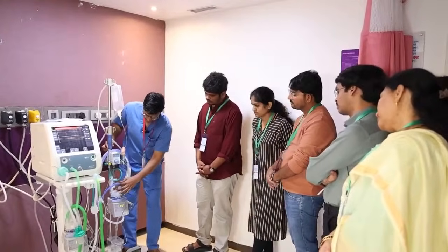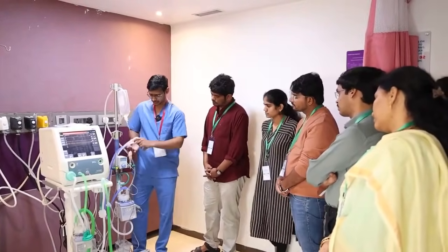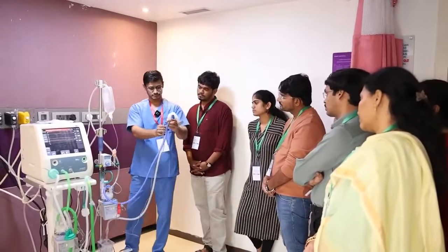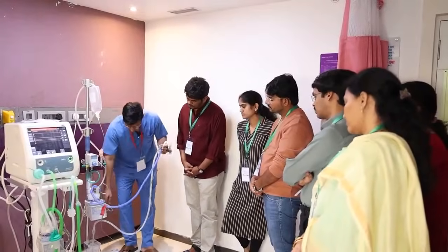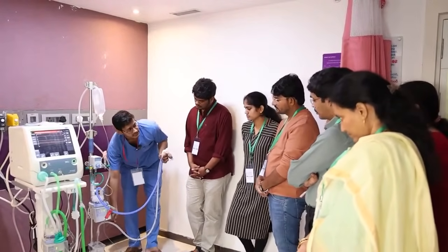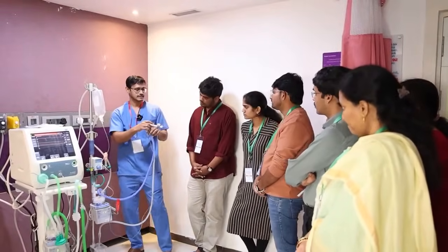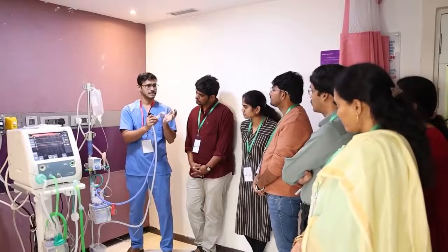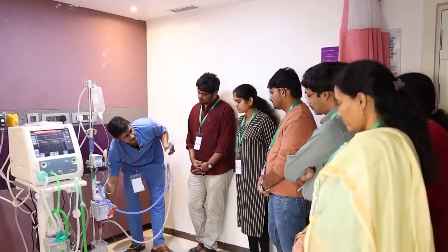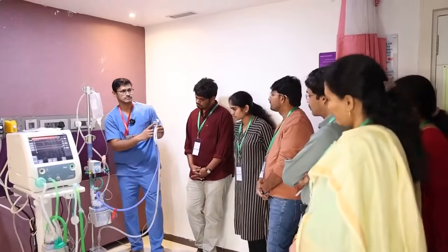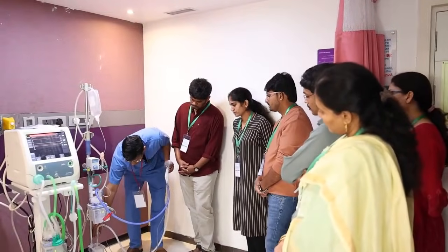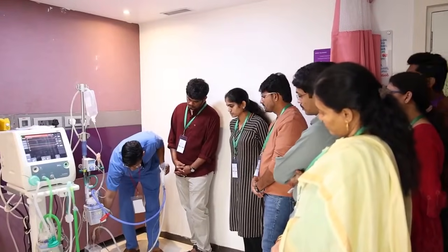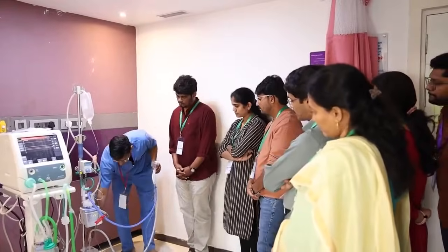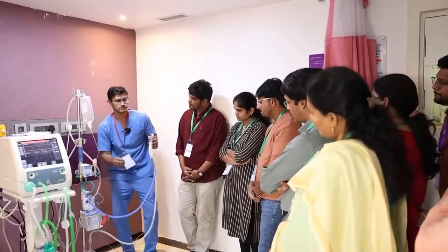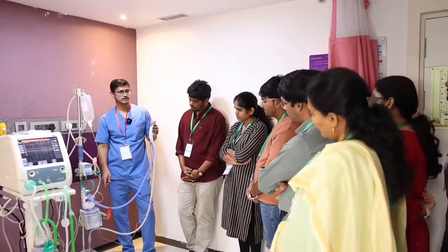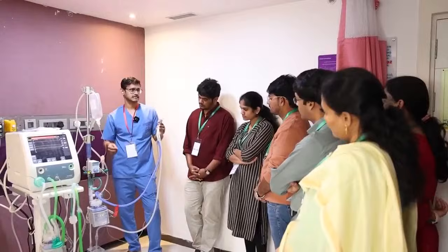From the humidifier you have an inspiratory limb, which is denoted in blue color, and then you have an expiratory limb here, which is the white one, and the expiratory limb is immersed in something called a bubble chamber. It is filled with water. So the pressure generated at the interface at the baby's end is based on the depth of insertion of your expiratory limb. So the pressure is generated in the expiratory limb. If you want to deliver a PEEP of 6, you immerse this tube to a depth of 6. And if you have to give a PEEP of 5, you take it out to 5. So the depth is very important. That's how you decide the PEEP which you want to give.